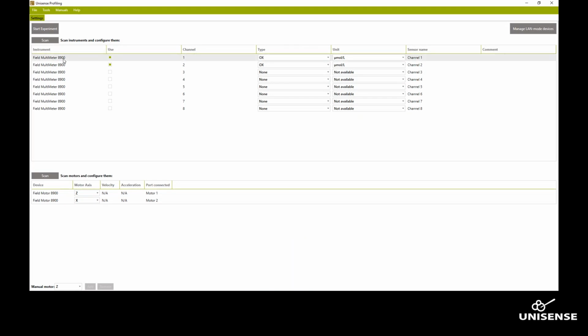And here it found a field multimeter with the serial number, and it has found that the field multimeter has 2 sensors connected. Oxygen sensors, both of them. I have 2 oxygen sensors with a tip diameter of 50 micrometer ready for this profiling. You can choose other sensors if you want. You see there are a lot of different ones you can choose from. Most of them will actually be recognized automatically, so you don't need to choose it. There are a couple where you need to choose it.